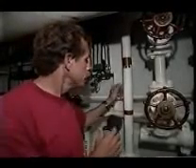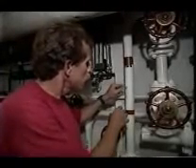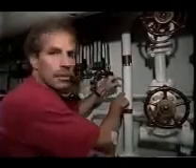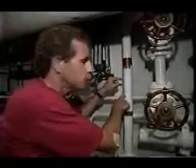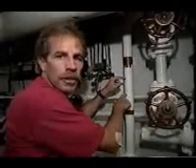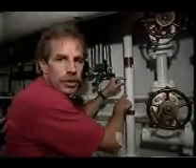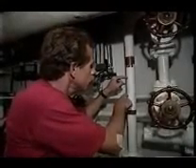Now essentially what this is, you put a blockage in a pipe and measure the difference in pressure before and after the blockage. If the blockage is appropriately designed for the fluid viscosity, flow rate, and density, then what you'll get is a pressure difference which is proportional to the square of the flow rate. Now the blockage can be a simple plate placed in a pipe flange with a hole in the plate, or it can be more sophisticated designs such as a nozzle or something that we call a venturi.